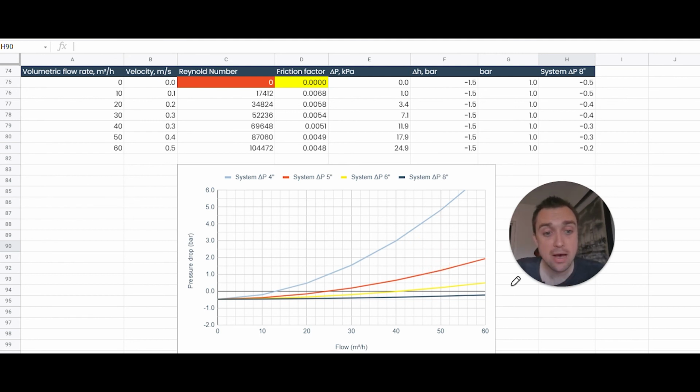And this is the entire point of a system curve. This system curve does not care where this pressure comes from. It doesn't know what pump is attached to it. It doesn't even know if it is a pump. The system curve is independent of the device that's supplying your pressure. The system curve says to you, you want 50 cubes of water an hour through this 4-inch pipe, I want 4.8 bar from you, and that's that. The cool thing about this is that we've done this to design a theoretically new pipeline, but I could also use a similar approach to evaluating pressure drops in existing pipelines.